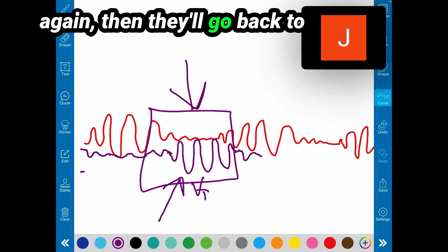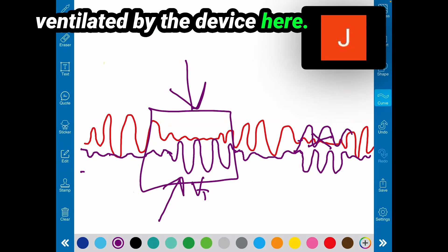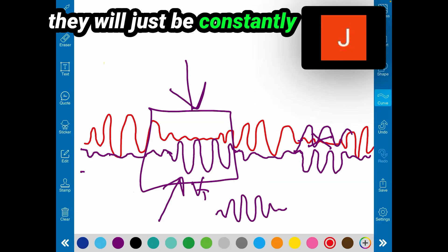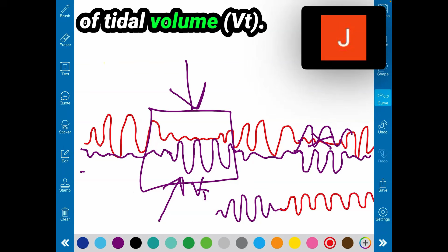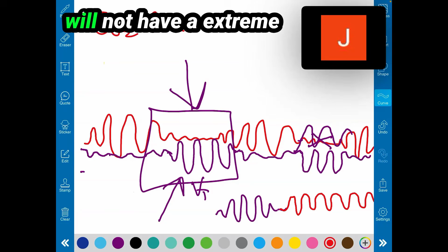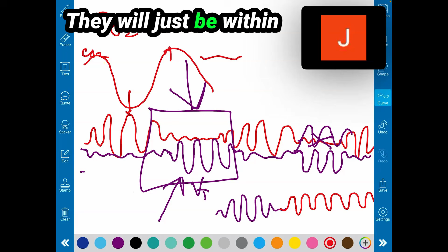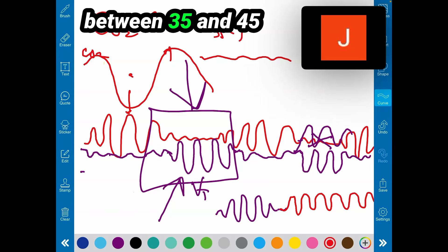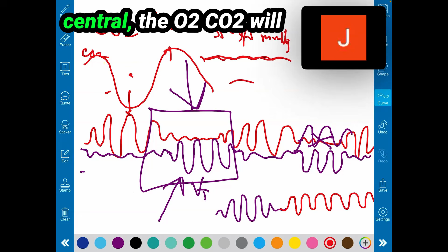And when the patient breathes again, then they'll go back to minimal pressure support. And then when the patient's having events, they will increase their pressure support. So now the result of this is the patient will eliminate the central because they will be ventilated by the device here. So instead of them having a crescendo decrescendo, they will just be constantly having the same amount of tidal volume. Okay, so then the CO2 and O2 will not have an extreme swing. Kung ito O2 to CO2 tsaka O2, they will not go too low, they will not go too high, they will just be within the normal range. Okay, CO2 primarily will be between 35 and 45 millimeters of mercury. So it will not cause a central. The O2 CO2 will be just on the right track.